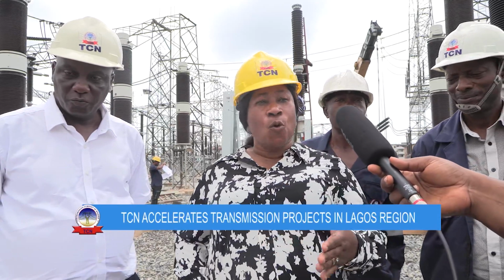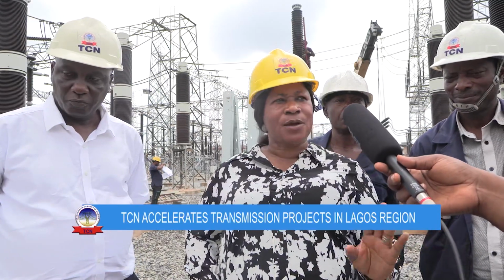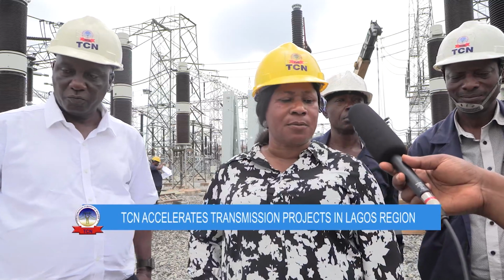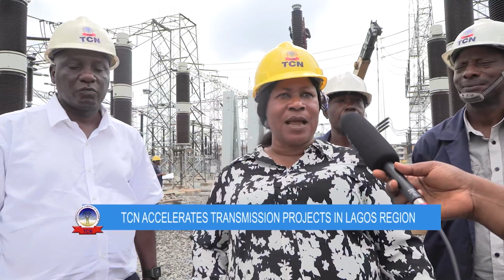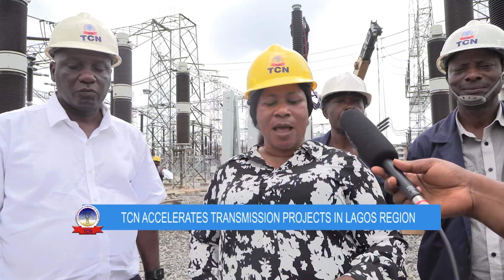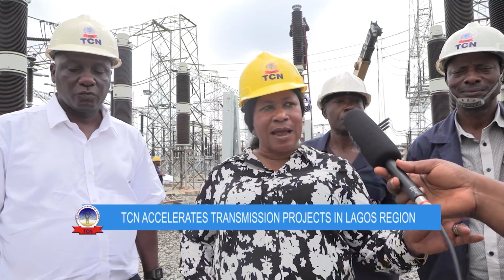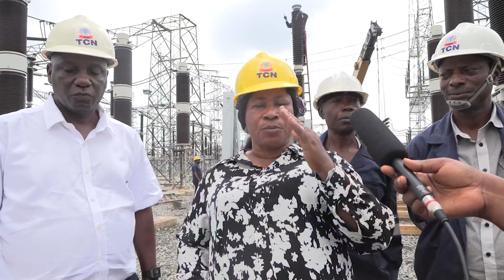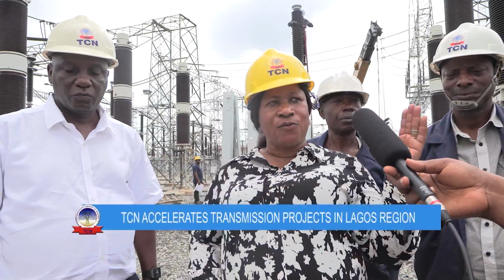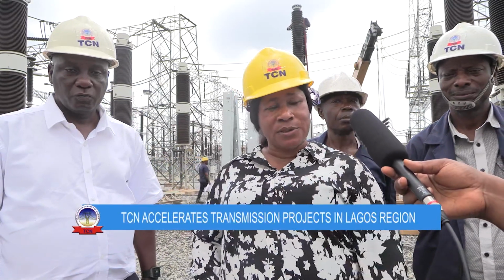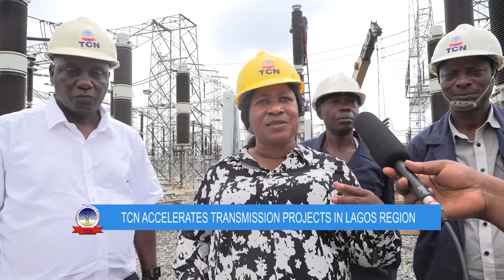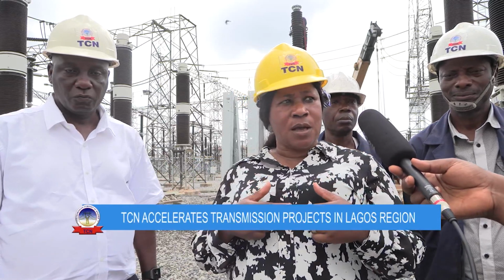We are replacing the old and defective bus coupler breaker, the 33 kV bus coupler breaker. We have 2 lines from Ikeja West - Ikeja West Akomba 33 kV lines 1 and 2, circuits W3L and W4L. W3L is attached to the main bus, and W4L is attached to the reserve bus, but this breaker is used to couple the 2 buses.